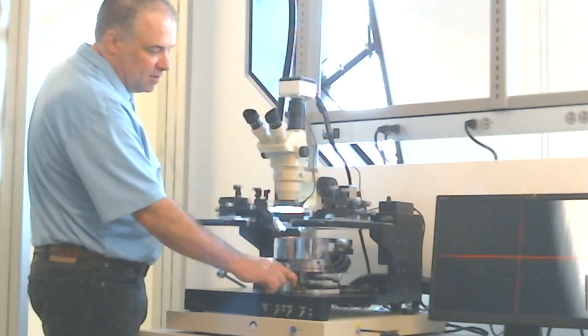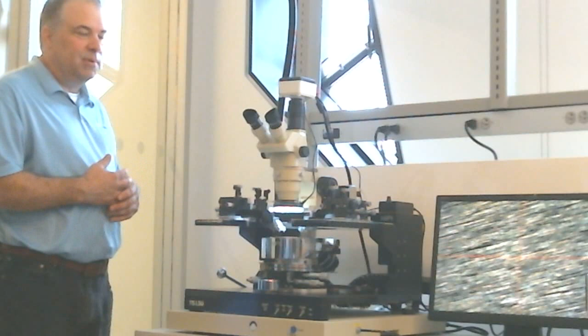It's very important to keep this surface clean from dust or grit or anything like that. If you get a little dirt on it, it may affect how smoothly it runs, may not run quite as smoothly. Clean it periodically. When you do clean it, use 100% alcohol, 100% IPA, with lint-free wipes. Do not use water, glass cleaner, solvents, or anything that would leave a residue. 100% IPA will not leave any kind of residue.